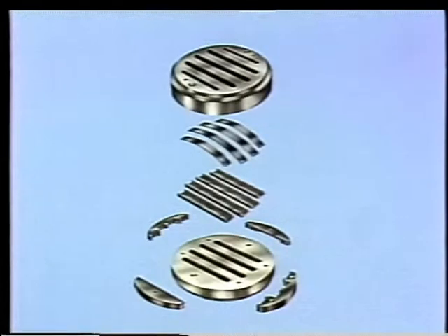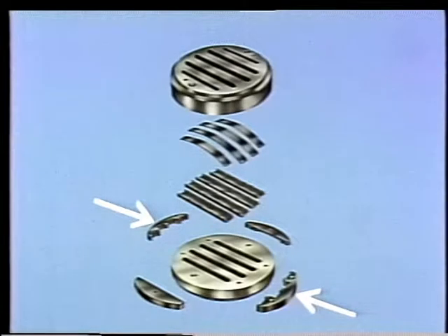Now, our third type of valve is the channel valve. This is the type installed in the compressor that we're going to overhaul. First, let's look at its parts and then see how the valve moves. A channel valve is made up of three basic components: a valve seat, a stop plate, and the movable parts, the channels. In addition, it has channel guides and leaf springs.